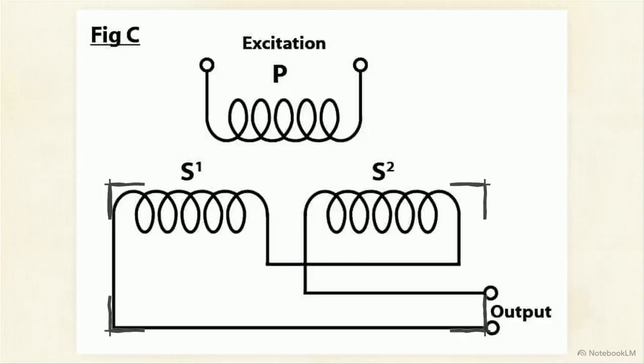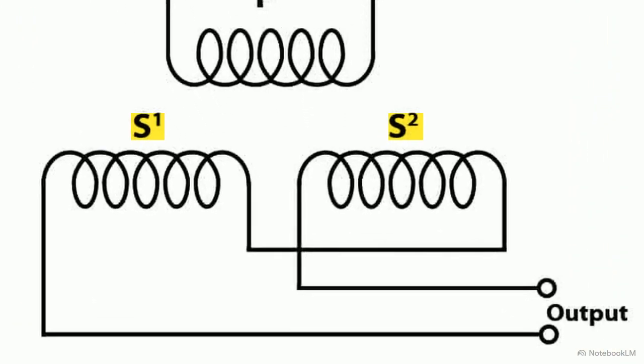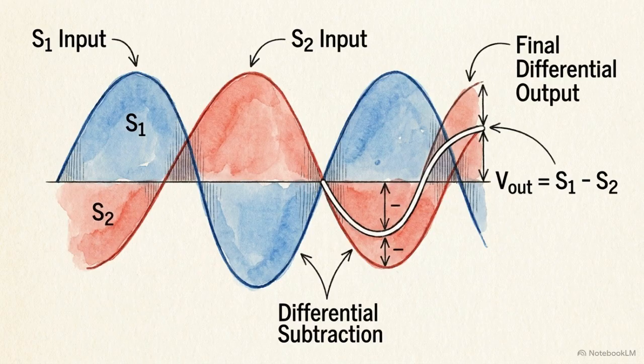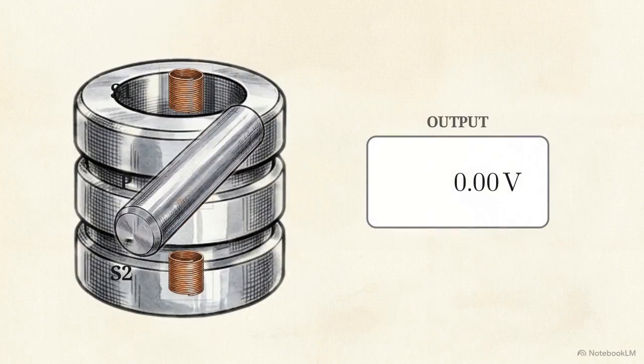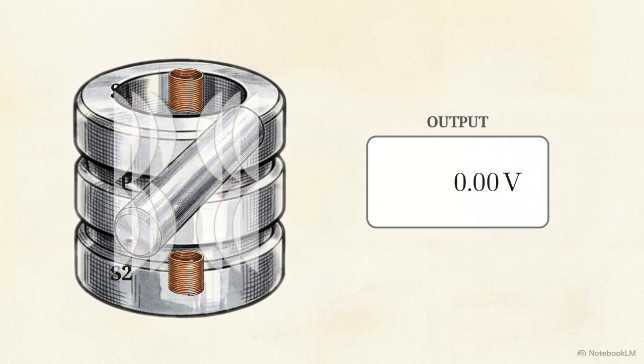The electrical schematic reveals the specific wiring logic that allows the LVDT to function. S1 and S2 are connected in series opposition, meaning the induced voltages in each coil work against one another. This results in a total output voltage, the exact difference between the two secondary EMFs. At the null position, the core is perfectly centered. The flux linking with both secondaries is equal, and the resulting output voltage is 0.